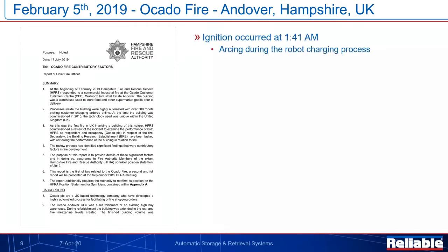Now, ignition of the fire occurred at 1:41 a.m. and that was due to arcing at the charging station for the robots. The robots incorporated a plastic top that through the process of arcing ignited. And it's basically believed that the robot was sent onto the floor after charging while it was ignited.